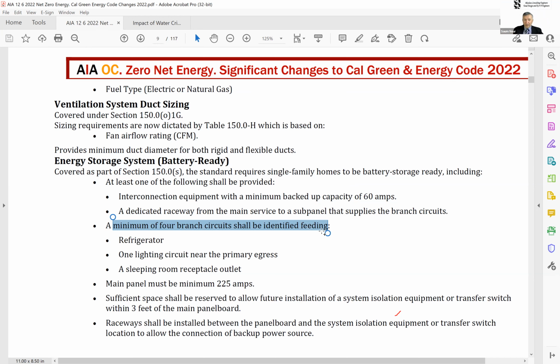One more item: in the National Electrical Code, they were asking for only 60 amp for a small apartment, 100 amp for a bigger apartment or a residence. So sorry—you will now have a system with a 225 amp panel as your minimum size. There's no discussion whether this house is 1,000 square feet. And by the way, up to 2,500 square feet with not much amenities, 225 will be fine.